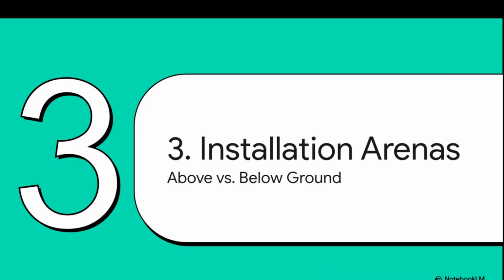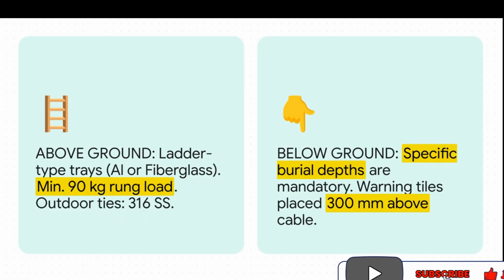All right, we know our materials. Now let's talk about where they go. Section 3 takes us to the two main battlegrounds for installation, above ground and below ground. And trust me, each one has its own unique rule book. So when you're working above ground, you're mostly dealing with ladder-type cable trays, and each rung needs to handle at least 90 kilos. Here's a tiny detail that interviewers love.